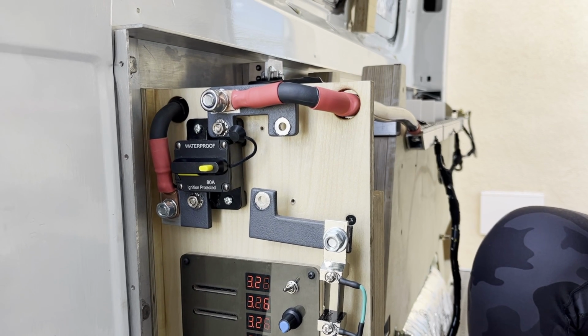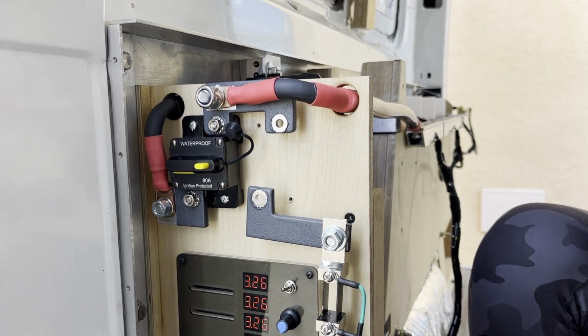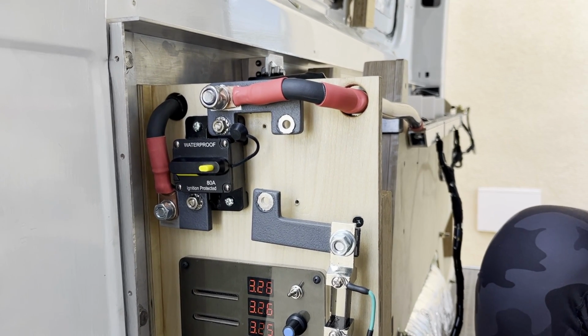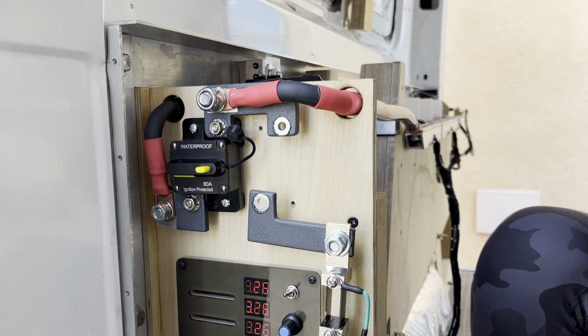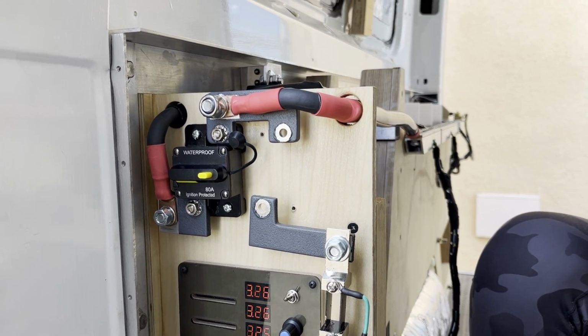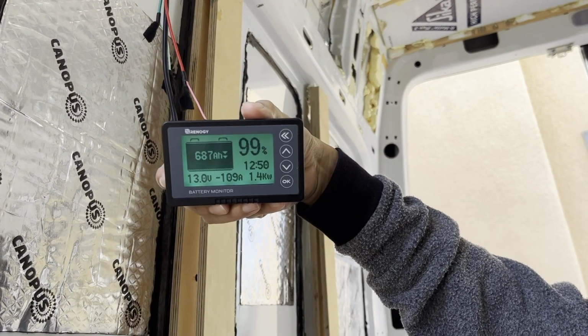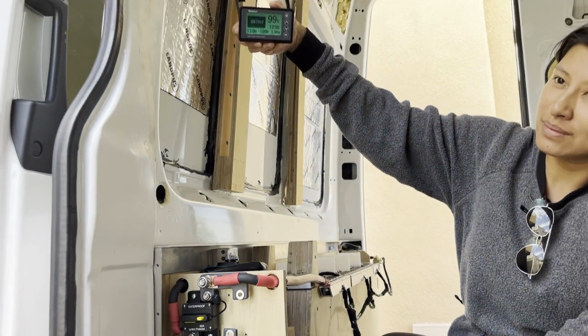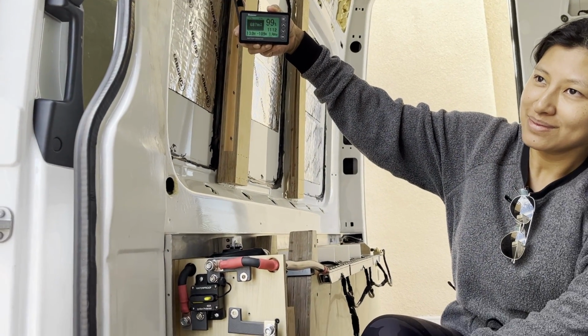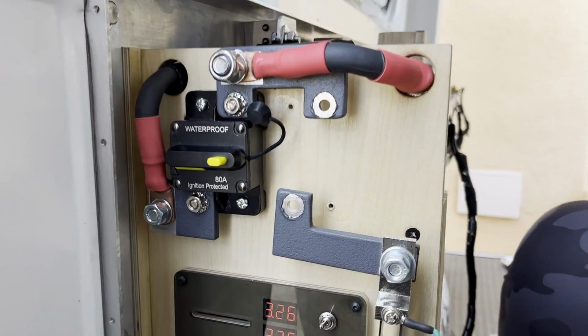And it should be popping. If you actually needed an 80 amp breaker, that should be popping by now, because that's 109 amps. At 109 amps your electronics might be dead by now.